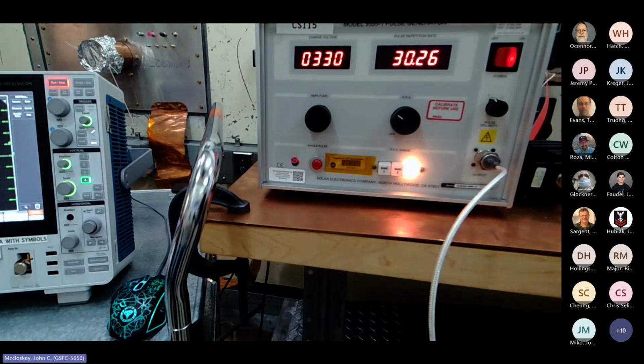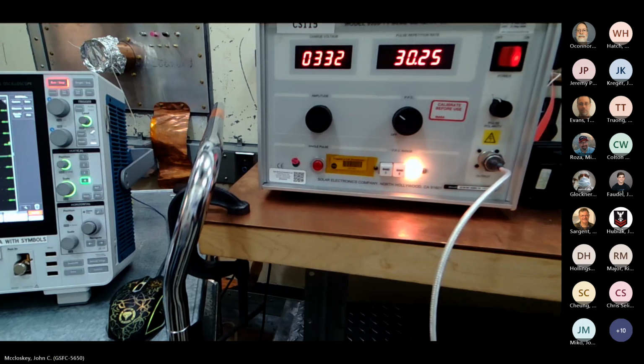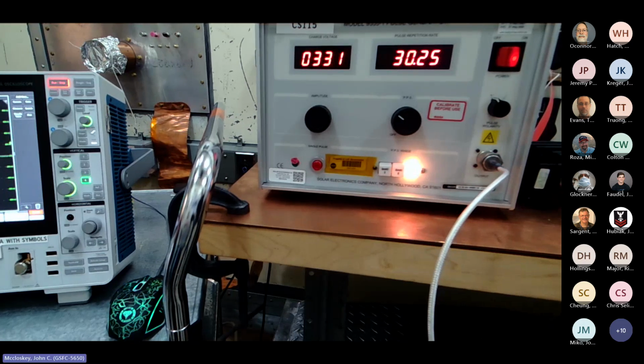We saw that with CS116. It was hard to really dial in a desired amplitude because any little change on the potentiometer knob was a pretty significant change in the signal level. So when you put some attenuation on, if you're looking for a smaller signal than what the unit's capable of, you put some attenuation on it, then you can drive the amplifier closer to the full scale where it likes to be, and use the attenuation to your advantage to get the signal down into the lower range that you want. So that's what I have for the CS115.